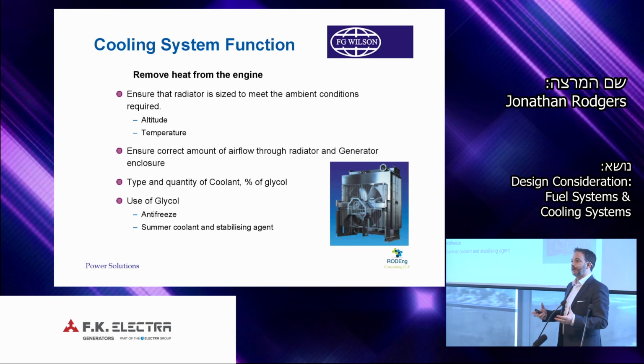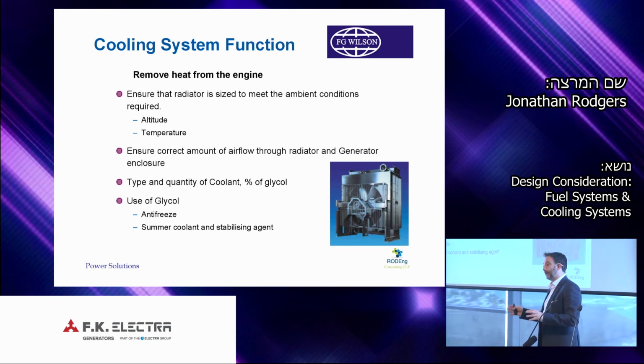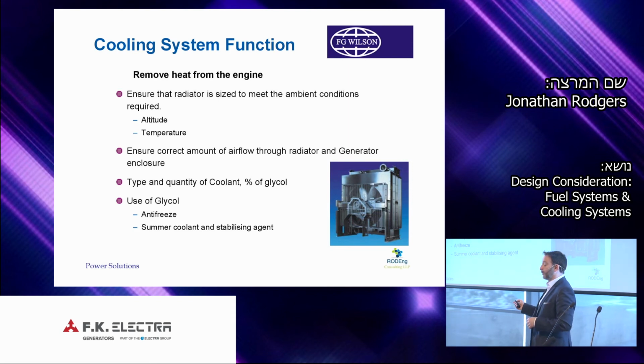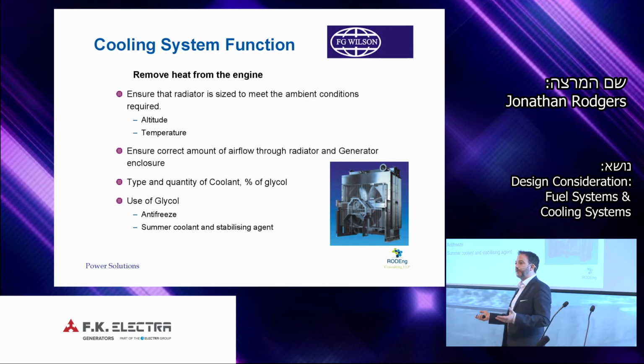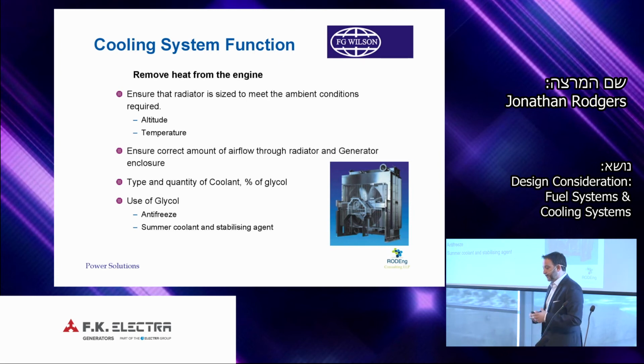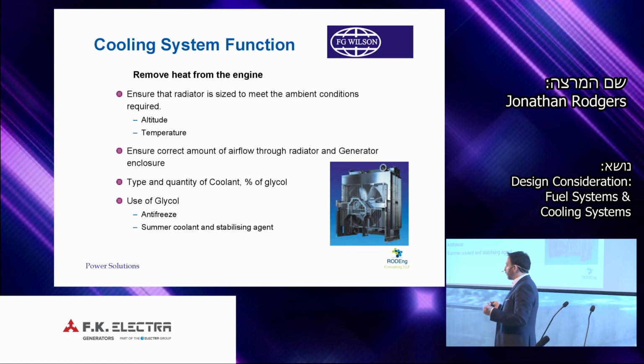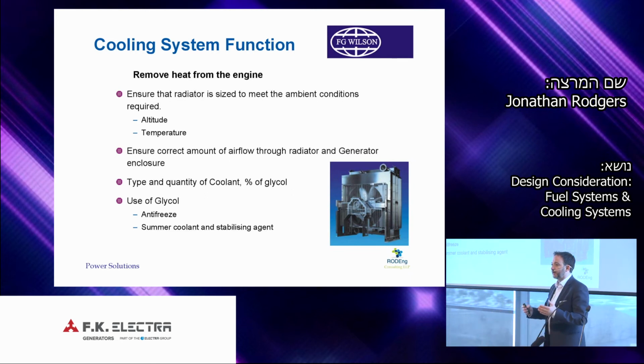When we're sizing the cooling group and the cooling capability and airflow, we need to look at both temperature, so maximum ambient temperature, and also altitude. Some engines will start to derate maybe 2,000 meters above sea level, some from 600 meters, but the cooling group will be affected at any altitude greater than 152 meters. So normally the airflow rate will not vary significantly, so it's not a major factor, but it's something we must consider.